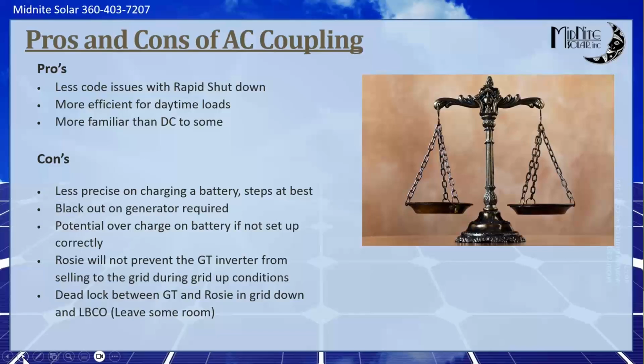And they run their battery down, and the inverter goes into low battery cutout. When I say inverter, I'm talking about the Rosie or your battery-based inverter. It hits that low battery cutout, and it ceases making 120, 240 because it's trying to protect the battery. Now, at this point, the grid tie inverter goes offline. So now you have the chicken or the egg issue here. And the only way to get that back online is to start the Rosie back up.